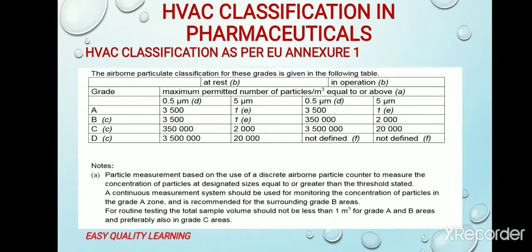EU Annexure 1 is specified for sterile dosage preparations. Here also, Classes A, B, C, and D are specified with the number of particles defined. The difference between Schedule M classification and European classification is that in European classification, one 5-micron particle per cubic meter is allowed in Class A and Class B, whereas in WHO classification, the number of 5-micron particles allowed in Class A is zero.